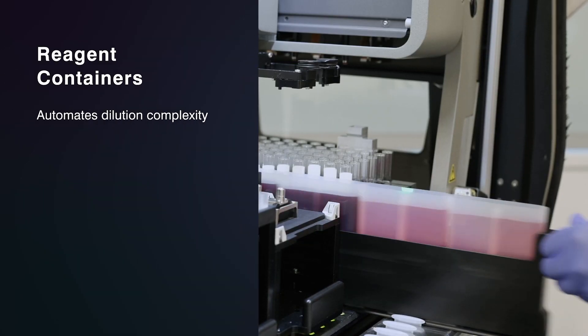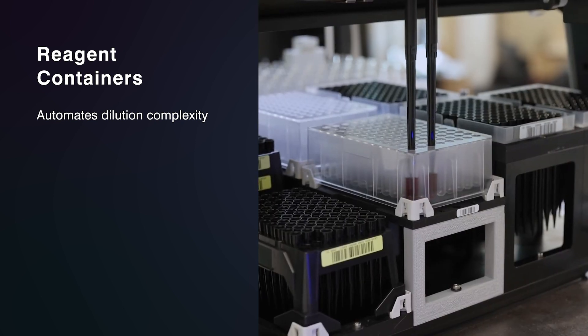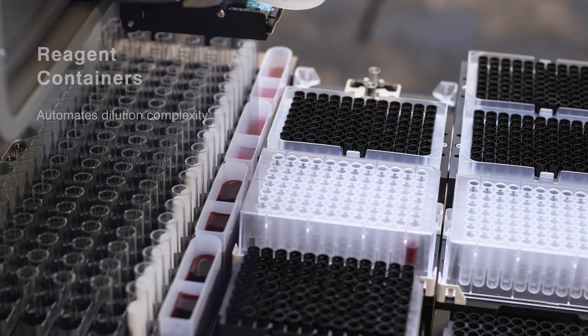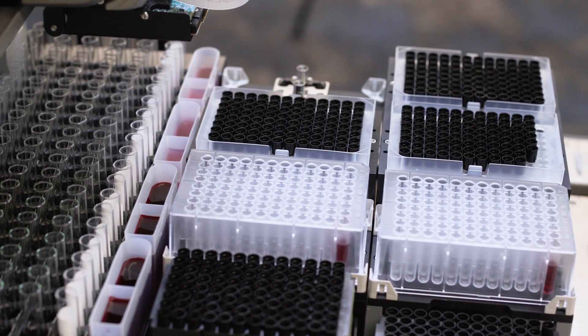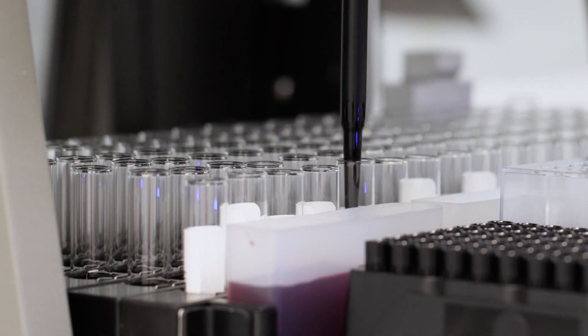Diluents are stored in 50 milliliter reagent containers. The system can make dilutions of up to 1 to 32,768 per sample. Each sample can have its own dilution factor and up to two diluents, allowing users to run multiple sample types and complex dilutions at the same time.